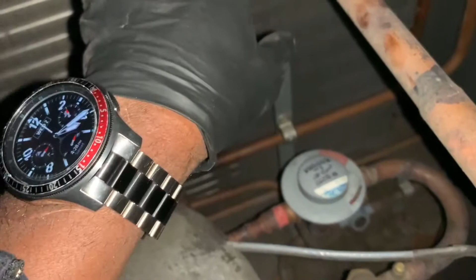So again, on the one hand, this valve, when the temperature and pressure is low, it will cause the blockage of liquid in the condenser, while simultaneously allowing the discharge from my discharge line right here to pass through, going directly into this liquid line, which is connected to the inlet of my receiver, and pushes out whatever liquid is in the receiver to continue to the system. Now, while that is happening, because the condenser is blocked off, we're not rejecting any heat, because we're blocking off the liquid line on the condenser. We're not rejecting any heat, so all the heat load absorbed or picked up on the evaporator side comes out as discharge gas. It comes straight into this barrel right here, which is your receiver. That's pretty much it. If you have questions, leave them in the comments. But that's about it for the operation, how it's piped in.